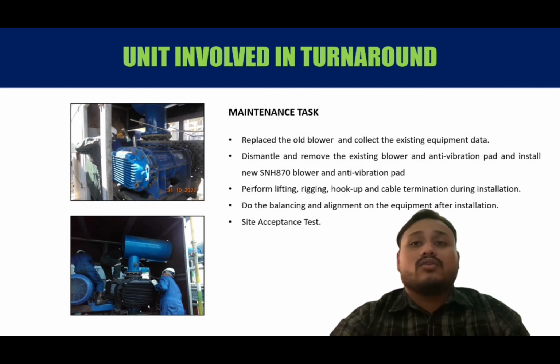Next, dismantle and remove the existing blower and anti-vibration pad and install the new SNH870 blower and anti-vibration pad. The new complete set of OptiBelt Red Power SPC 3750 belt with its 400 mm 3-groove pulley is also installed. We need to evaluate the adequacy of the anti-vibration pad design against the expected equipment assembly load. Then, perform lifting, rigging, hookup and cable termination during installation, where we shall supply competent manpower, tools, consumables, support services such as scaffolding, and transportation such as lorry, crane and forklift for the installation work.